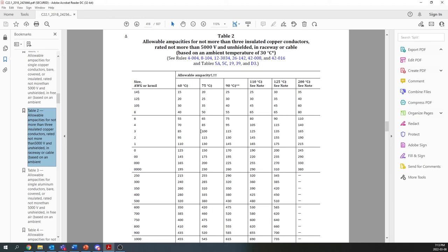So actually, we have to go up even further, to a number 3 conductor, 100. So 100 times 0.91, applying our temperature derating factor, times 0.8, is 72.8. Wow, even that's too low. Go up another one, number 2. That's 83.72. So you see here, we've gone up two wire sizes. Number 2 is not quite double a number 4, but it's a fair bit bigger, which means, of course, more cost.